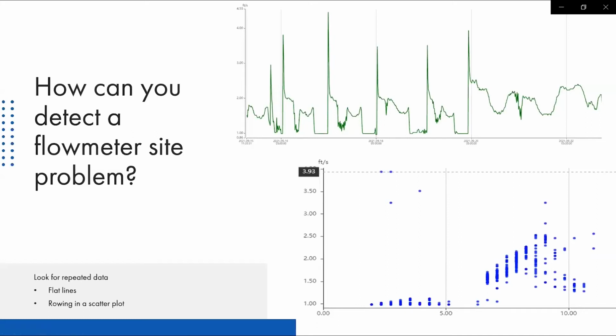And then you need to investigate what the problem is. These readings here with these flat lines, I believe it was because the water depth was too low. It wasn't able to pick up the velocity reading, and so then it just flatlined. But they're just things to keep in mind when you're looking at your data.